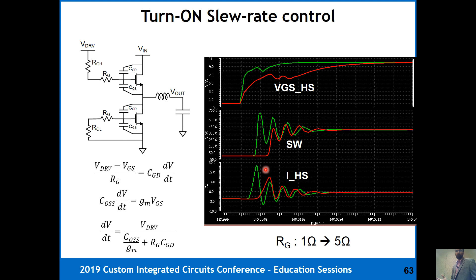And this is where the gate drive control comes into picture. So you try to increase the gate drive resistance to reduce the slew rate because of the presence of significant parasitics in your power loop, and that reduces the ringing levels to a more manageable value, so you can use conventional 600 volt MOSFET devices. Of course, it comes at the penalty of efficiency, because now your slew rates have reduced and your overlap losses go up.